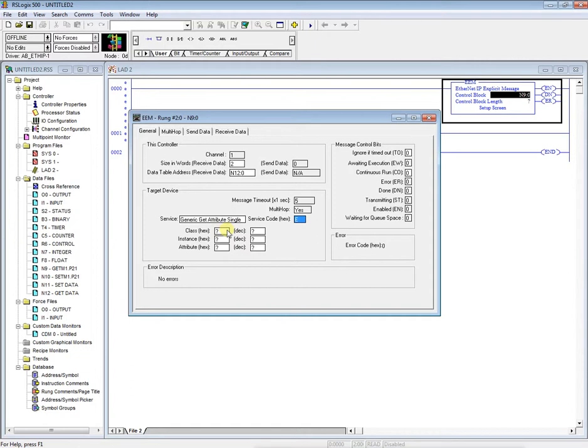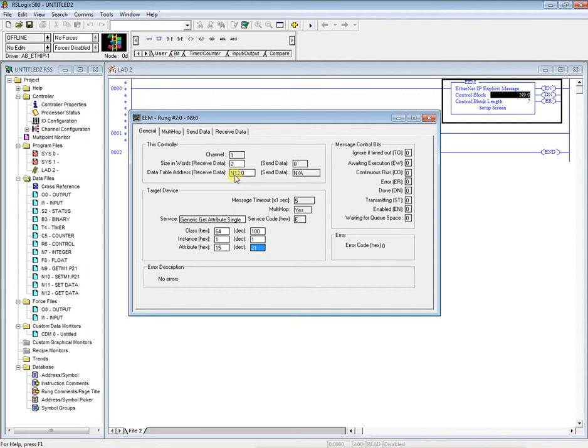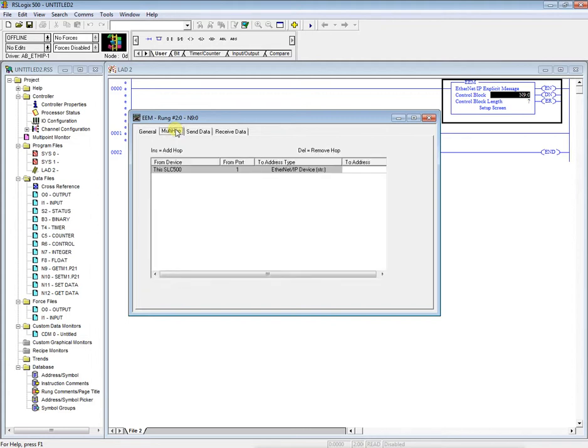And then the class. And over here in the decimal, we're going to change this to 100. It will always be 100 for our Unidrive M. The instance will be the menu. So we're working with menu one. Then parameter 21. Enter. So now we have our size and words received. Where do we want to store the information that we are receiving? And then the get attribute, instance, menu, and then parameter. So we'll come over here to multi-hop.